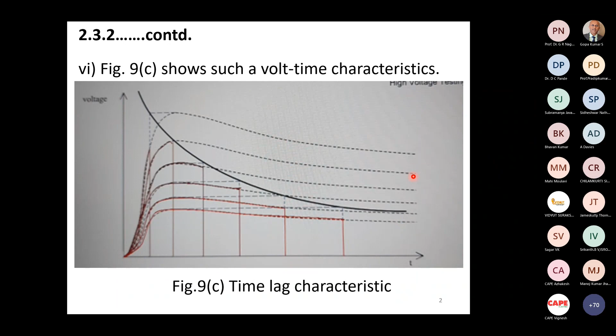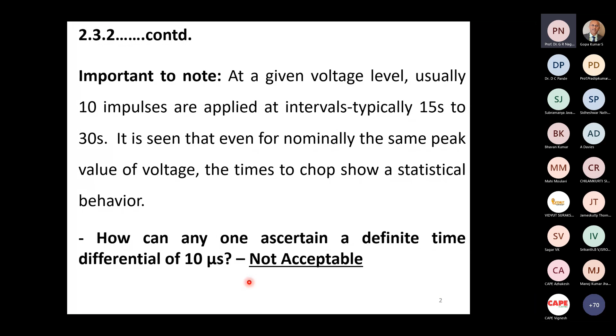So just to repeat again, at a given voltage level, usually 10 impulses are applied at intervals of 15 seconds to 30 seconds. It is seen that even for nominally the same peak value of voltage, the times to chop show a statistical behavior. How can anyone ascertain a definite time differential of 10 microseconds? It simply cannot happen. Therefore, it's simply not acceptable.